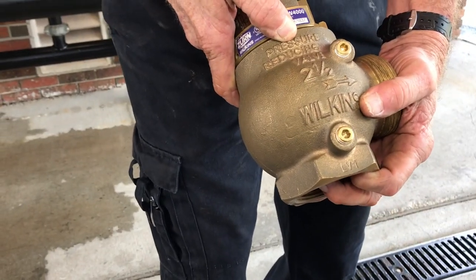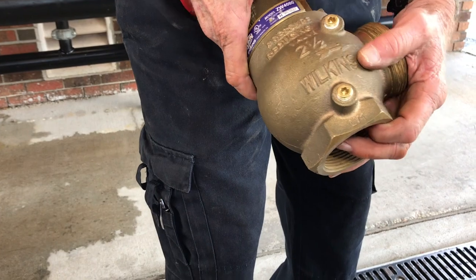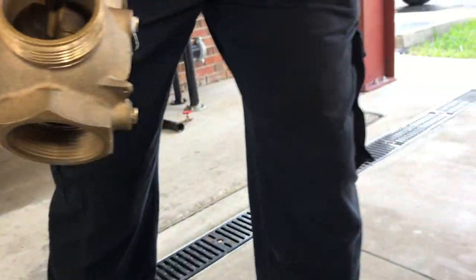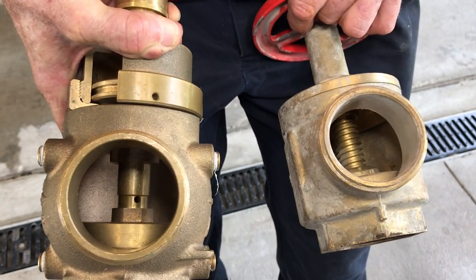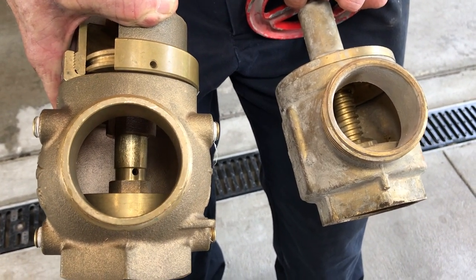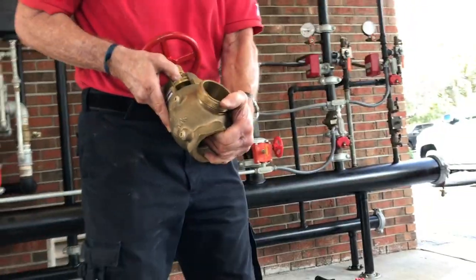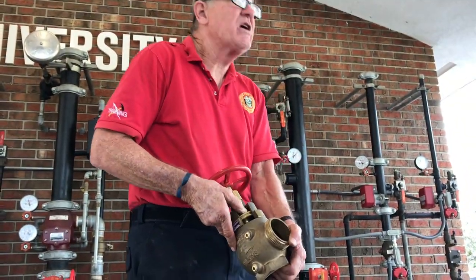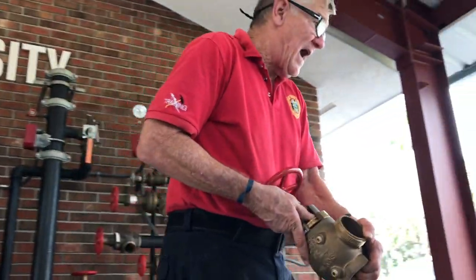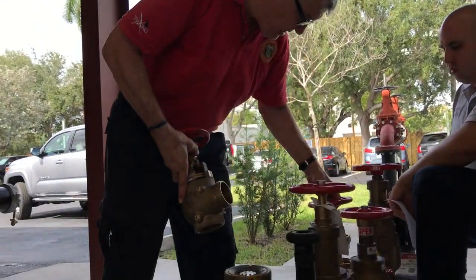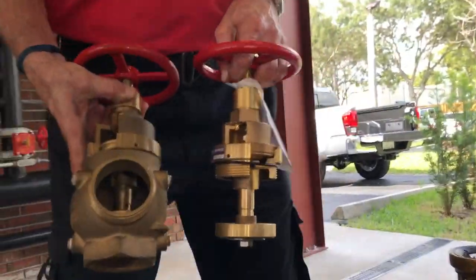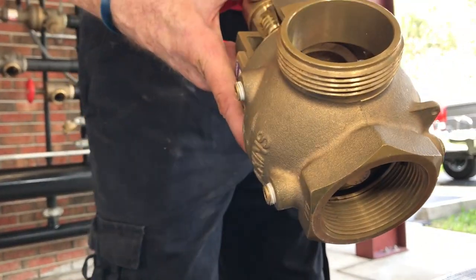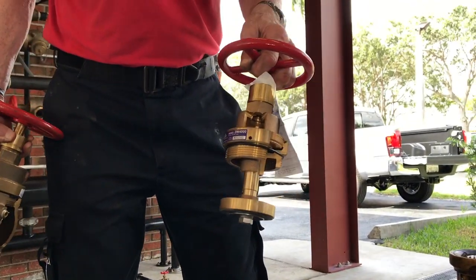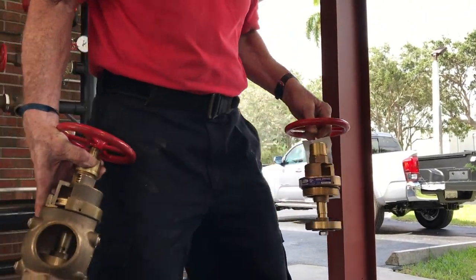Pressure reducing valve. I know of no PRV that does not say pressure reducing valve. One of the dead giveaways is this: threads, no threads. Threads on the conventional, no threads on the pressure reducing valve. Now, the pressure reducing effect of this valve is determined by the surface area of this piston. If you were to look at this valve, you see that this piston is smaller. Hence, this would be installed on lower floors. This would be installed on upper floors where the pressure would be less.